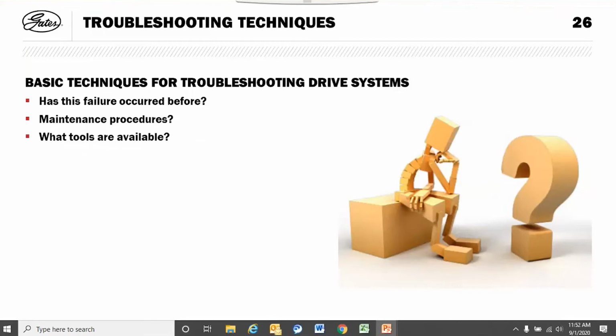If they're just tensioning it with what a lot of guys call the calibrated thumb, if Dave or I or Sean go to tension the belt with our thumb, all three of us are going to come up with a different tension rating. But we have various tools, pencil testers, what they call them, or sonic tension meters. That's the best way to tension a belt, so you take the subjectivity out of it.